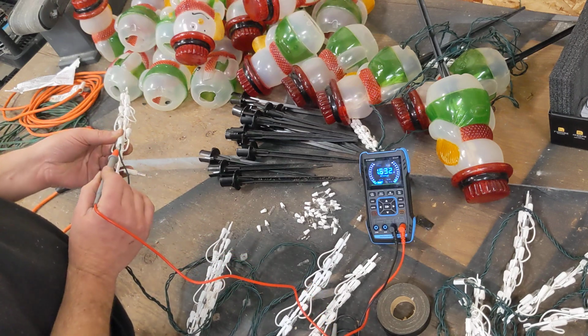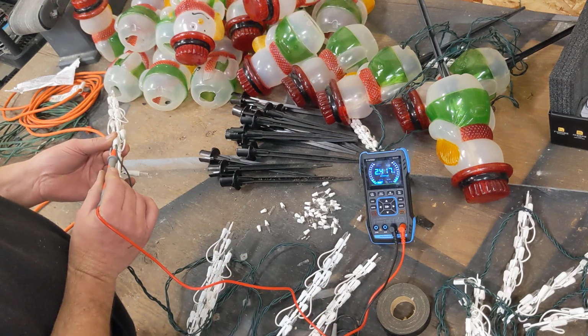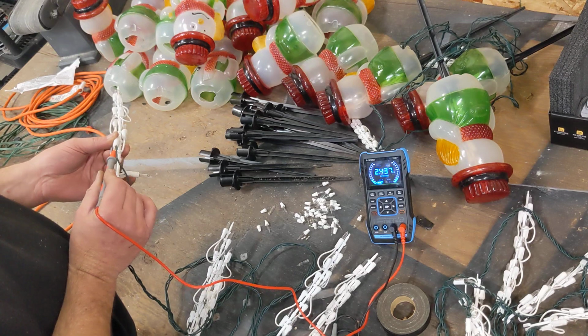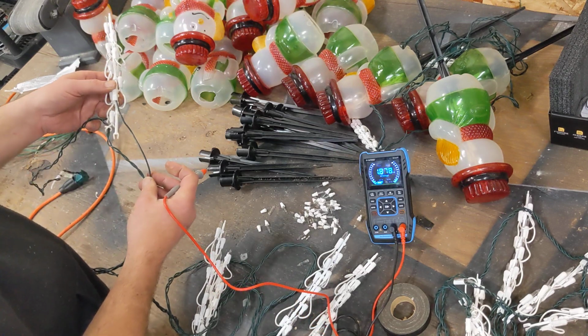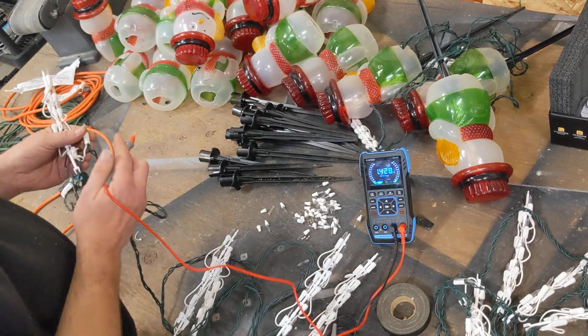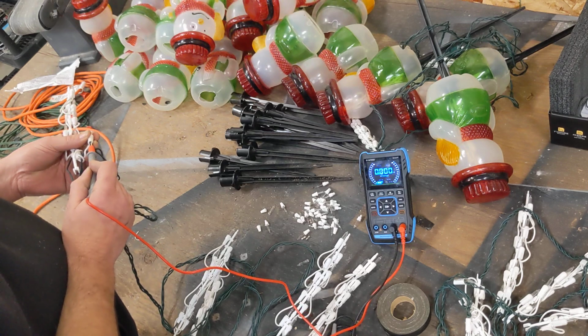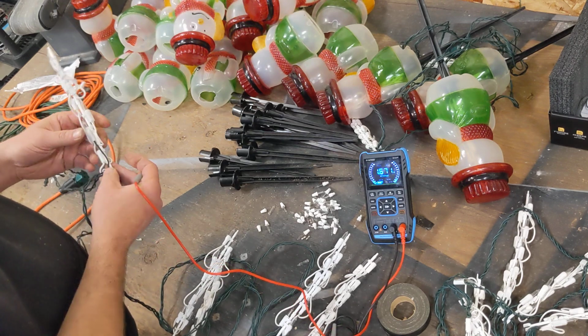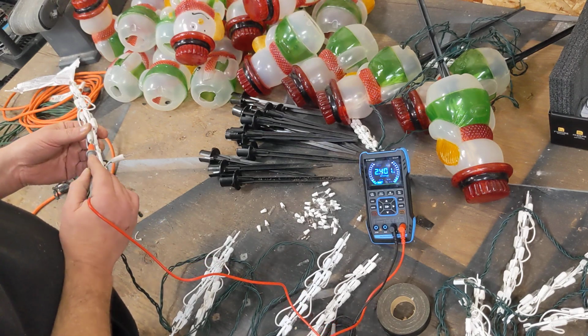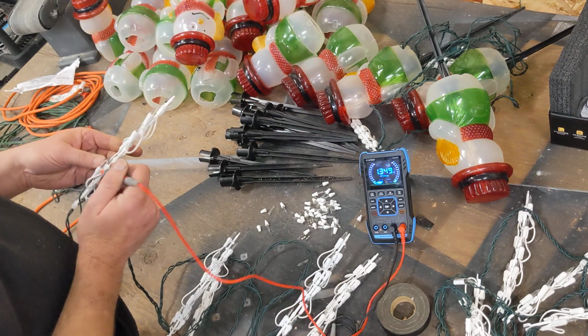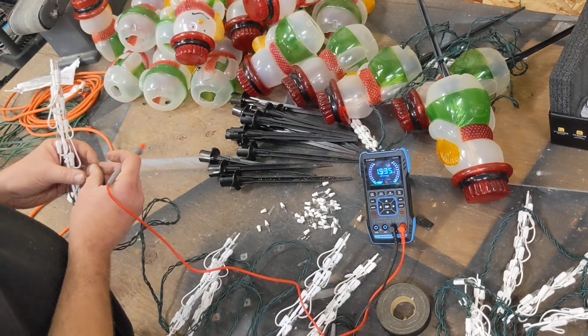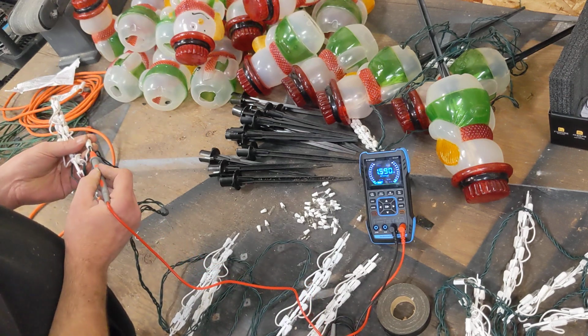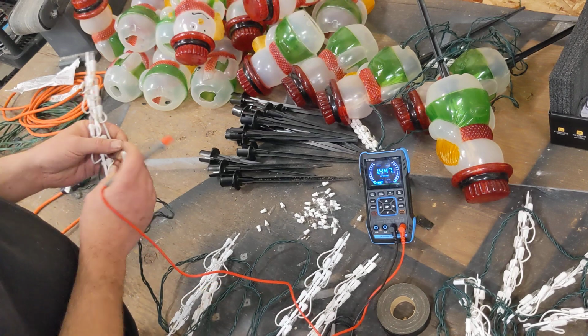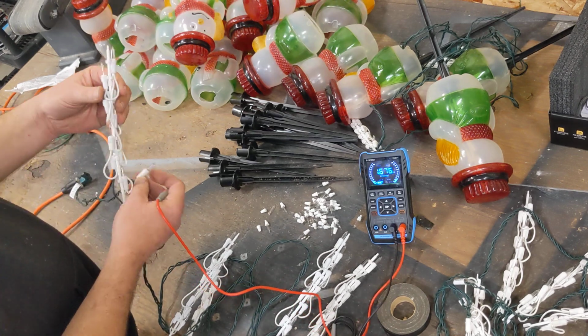Wire coming in from the last set... no, that's the final wire going out. Zero. So we got 120 volts in, but do not have 120 volts coming back out. So the problem exists somewhere within this string.